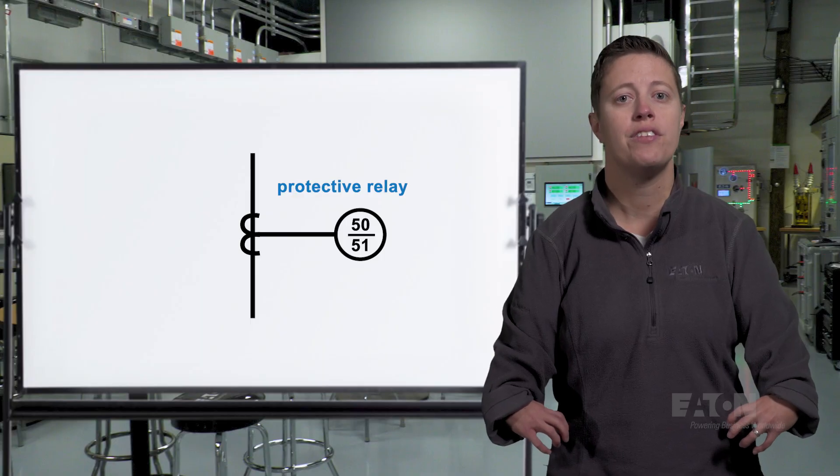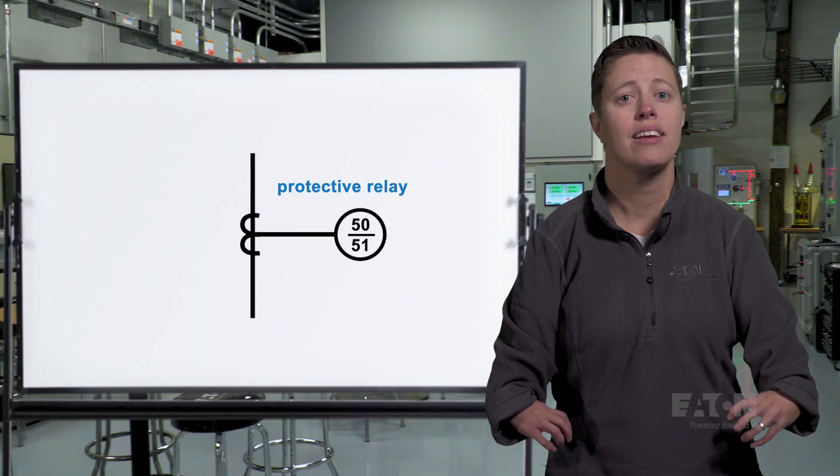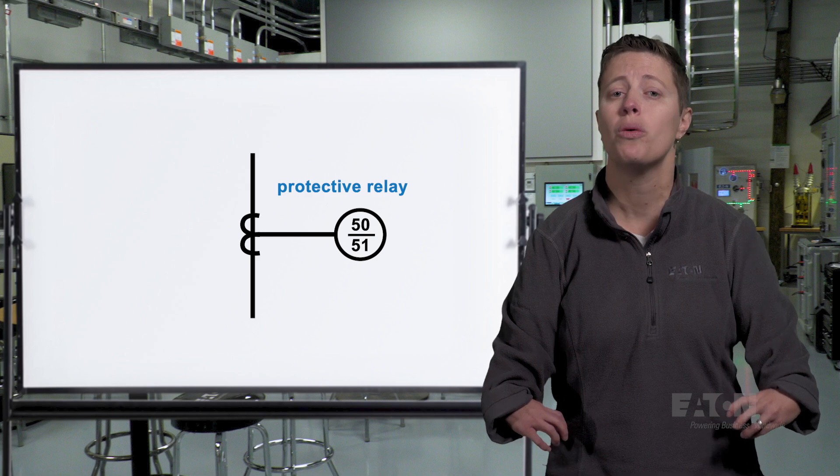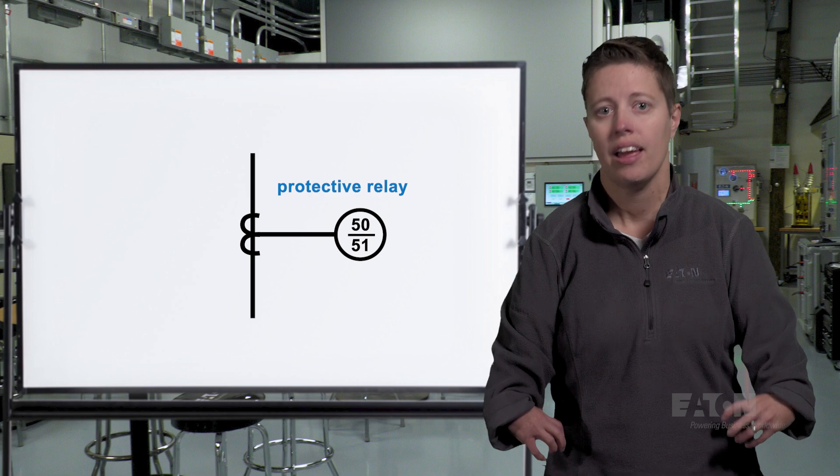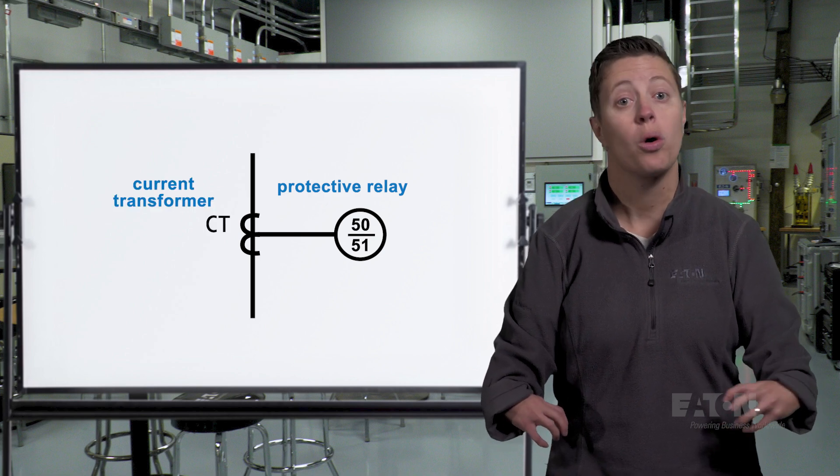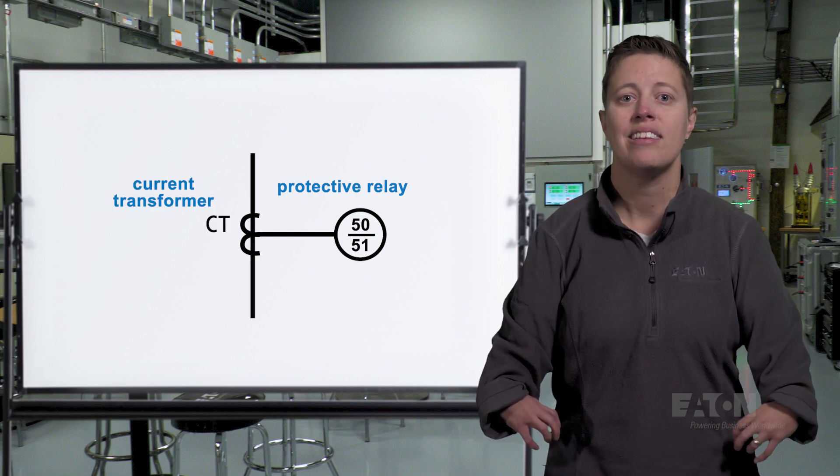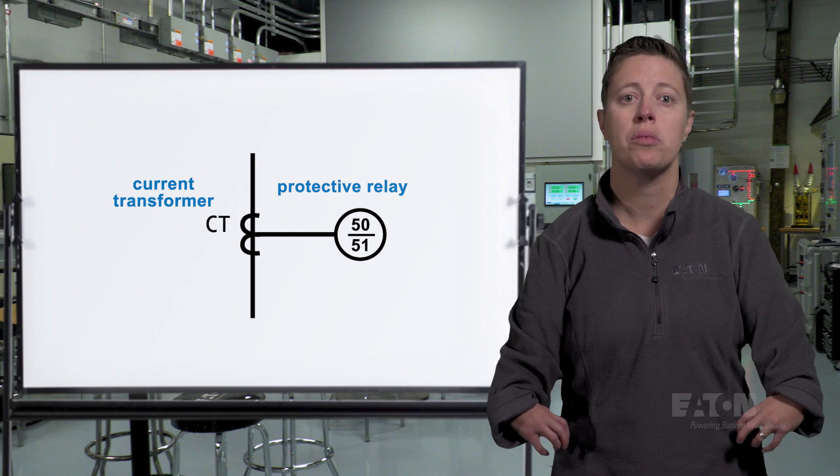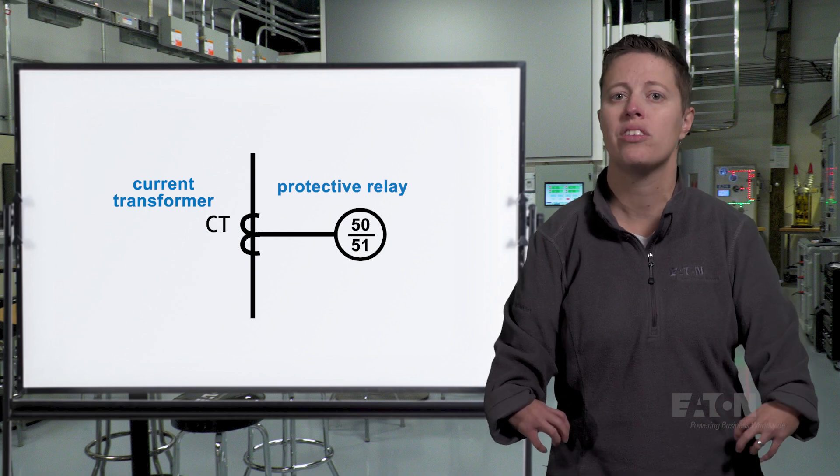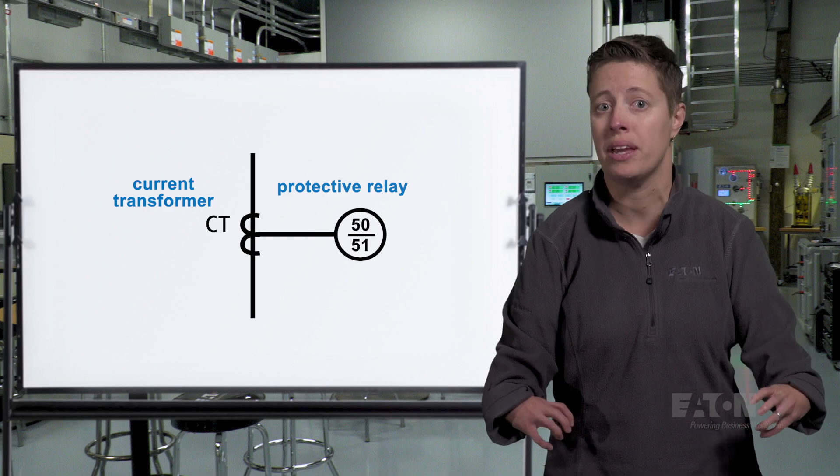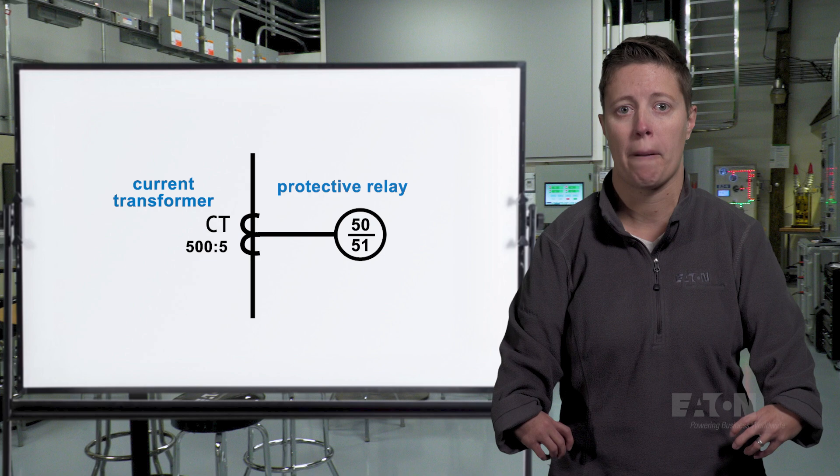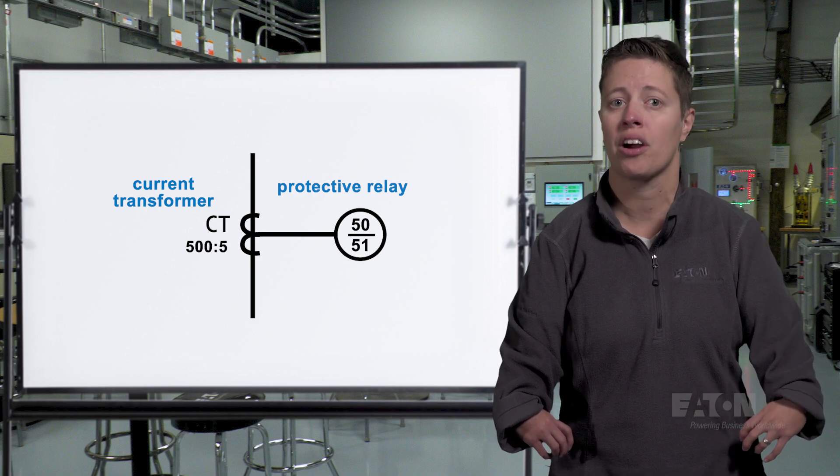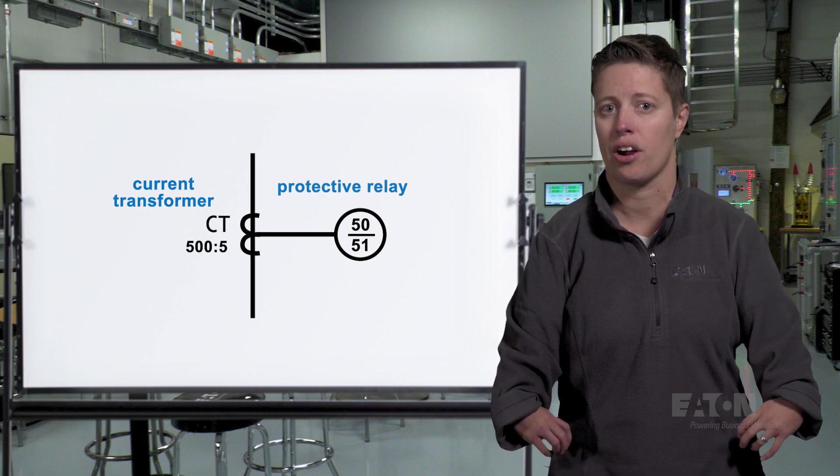You will notice the 50-51 notation is connected to the main circuit through two half circles end-to-end with a line extending from the center. This is a current transformer or CT. The CT takes line current and transforms it to a lower amperage to be safely read by devices like protective relays and meters. The CT ratio may be noted on the single line as well. This is the ratio of line current to CT secondary current.